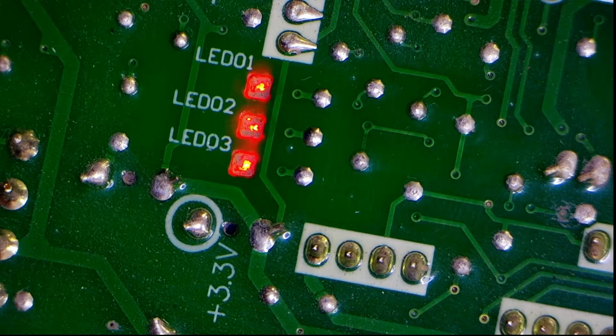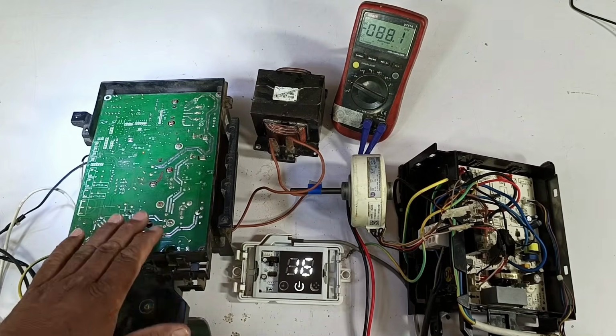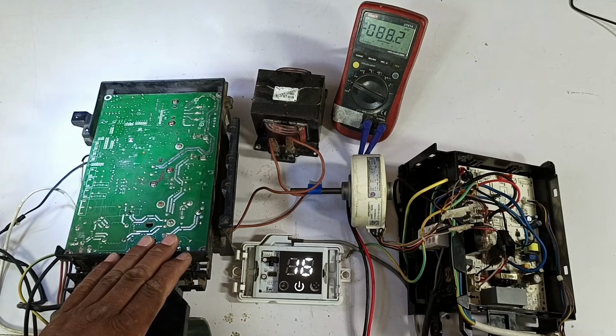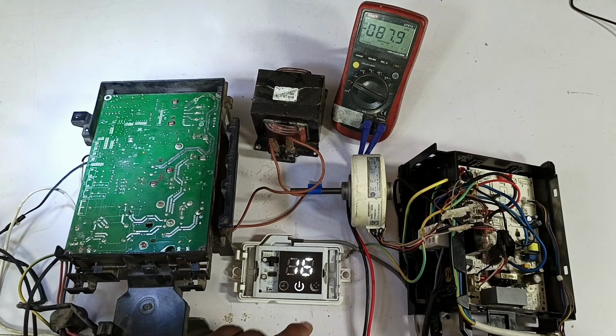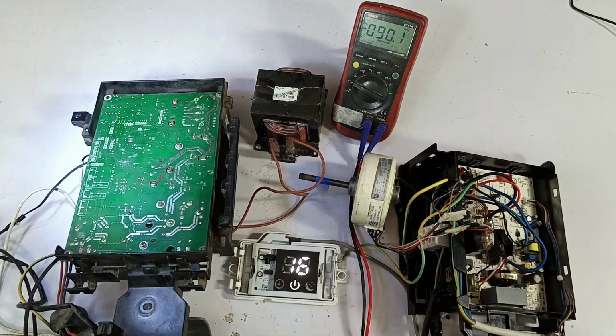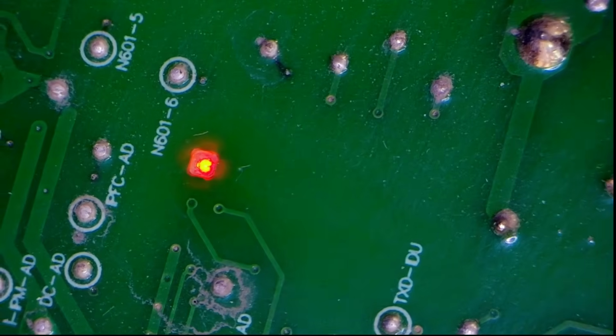As soon as I gave the electric supply, you can see here LED 1, 2, 3 of the outdoor have also turned on, and the indoor display has also turned on. Now, both PCBs are working, but still they are creating an issue. So let's see what issue is coming here. The fan motor has also started running, while its outdoor LED is continuously running here.